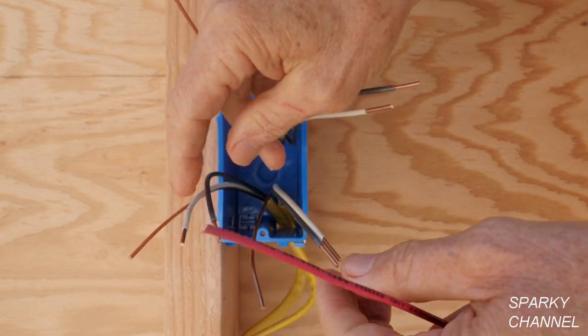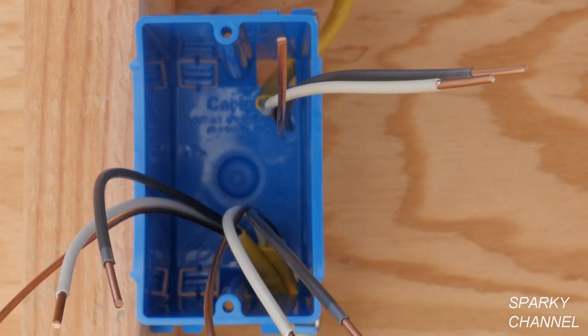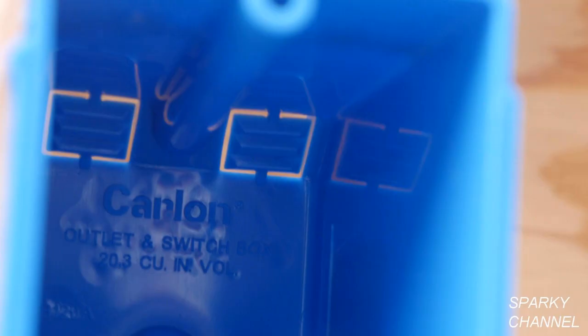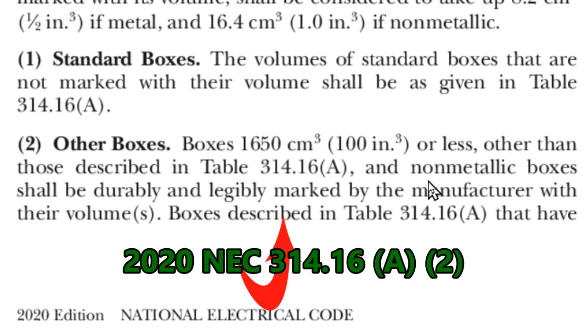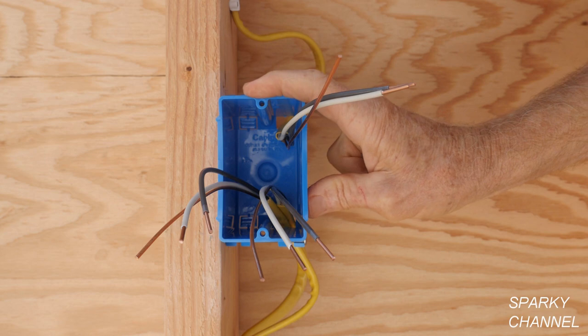So that means one, two, three, four, five, six conductors. The black and the white wires are conductors, and then we have three ground wires. So the first thing we need to know is what is the cubic inches of this box? It states in the code that all plastic boxes have to be stamped inside. This one says 'Carlon outlet and switch box 20.3 cubic inch volume,' per article 314.16A2. Non-metallic boxes shall be durably and legibly marked by the manufacturer with their volumes. So we can't go over 20.3 cubic inches.